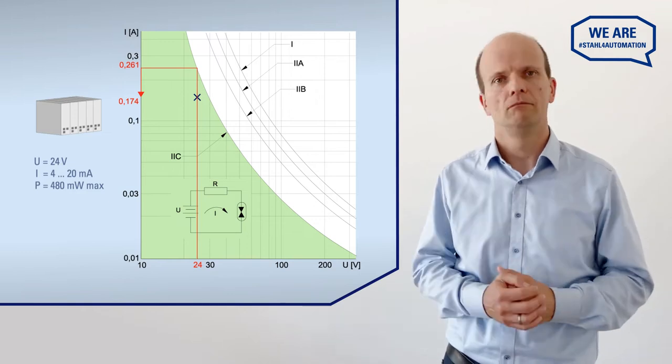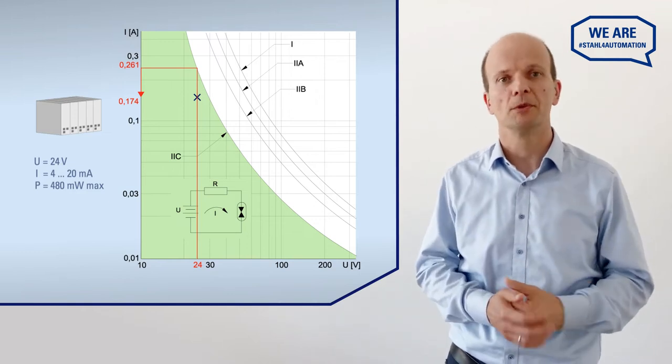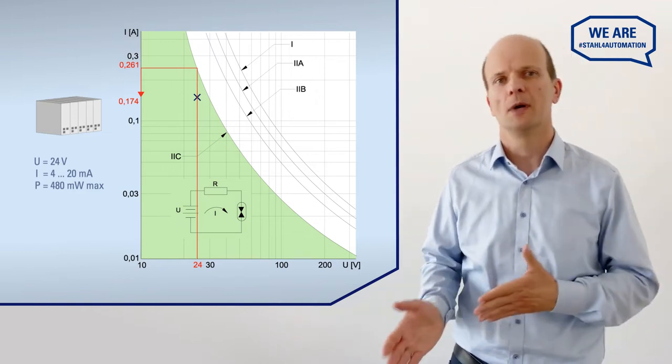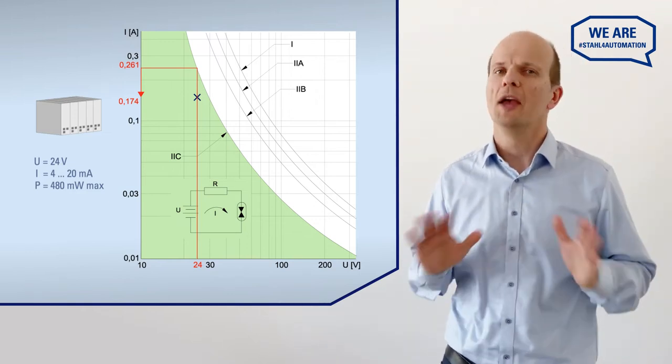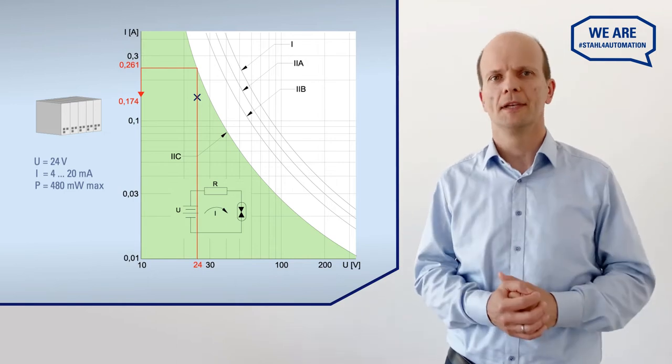We need to apply the safety factor of 1.5, and so we end up at around 174 mA. Our signal only carries between 4 and 20 mA, so we are definitely safe at this end.